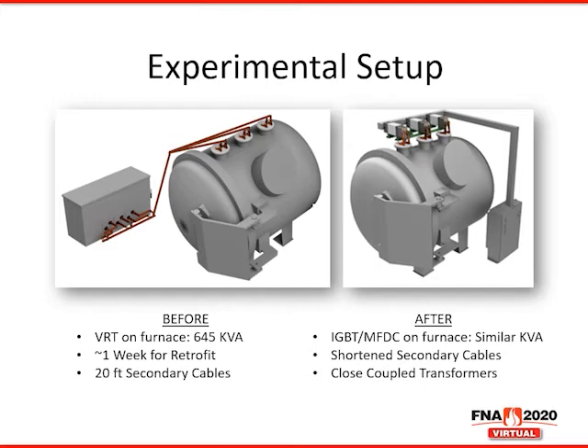Here you can see the details of our retrofit. On the left, we have the VRT and vacuum furnace as it was originally. The VRT was rated at 645 kVA and had approximately 20-foot long water-cooled cables that went from the VRT to the power feed-through on top of the furnace. It took approximately 1 week to remove the VRT and place our IGBT MFDC system, which you can see here on the right. A couple things I want to point out here. One is the MFDC transformers are located on top of the furnace near the power feed-throughs. This is an important part of our value proposition that I'll get into later, but take note of that.